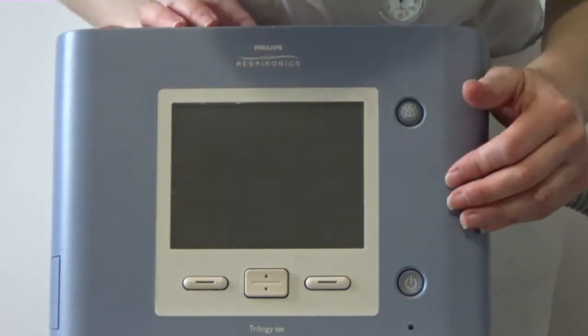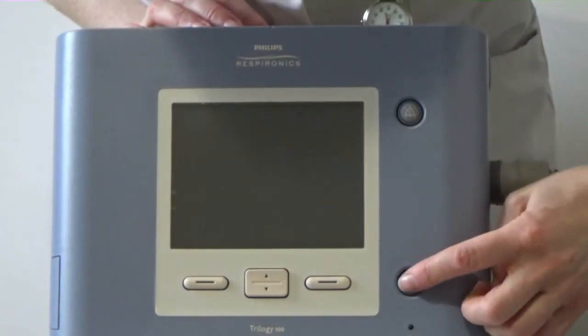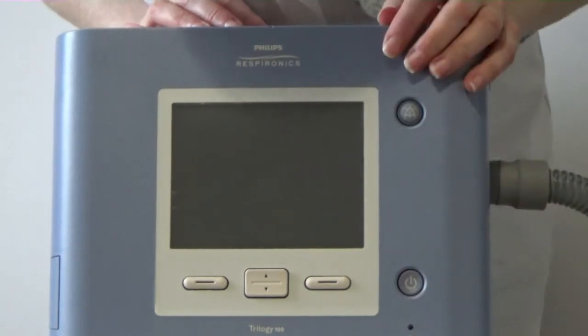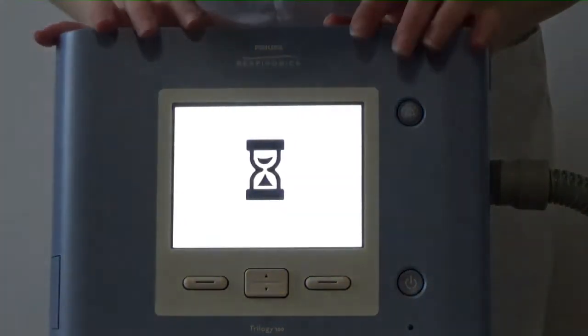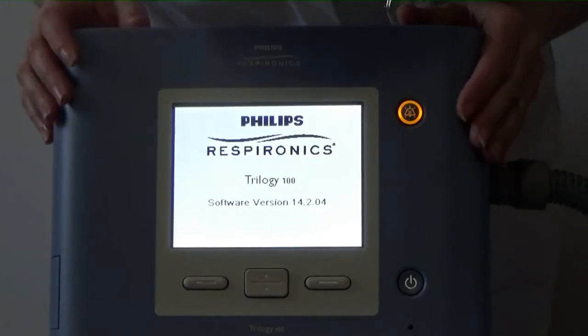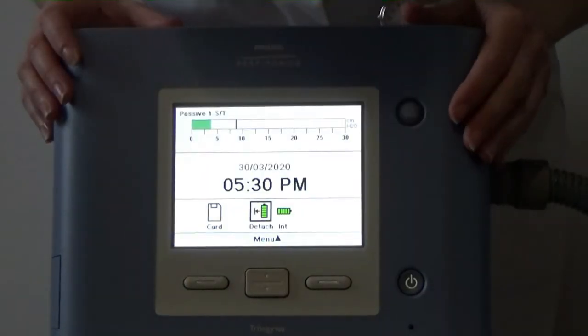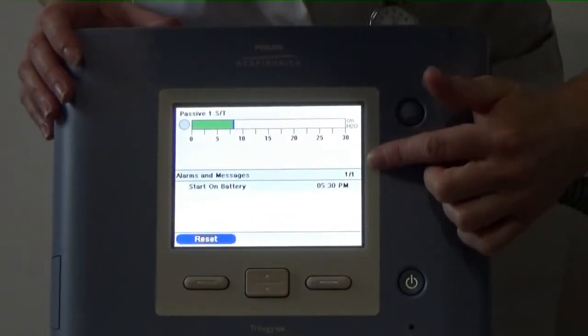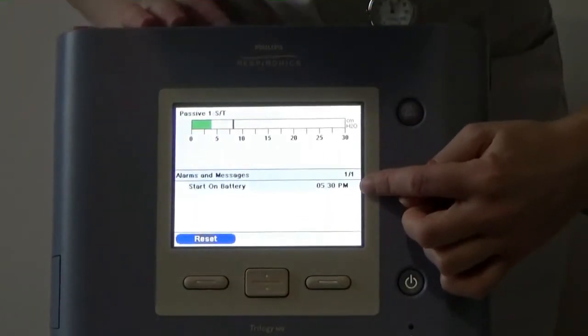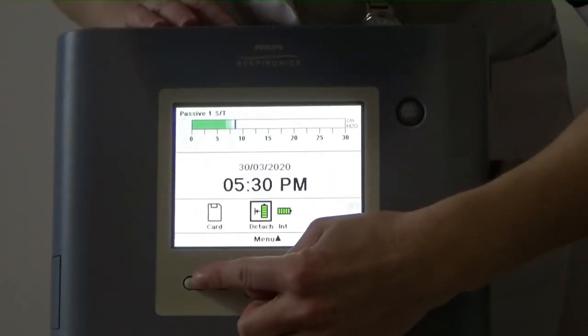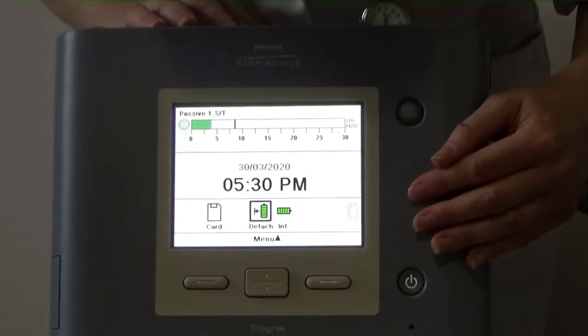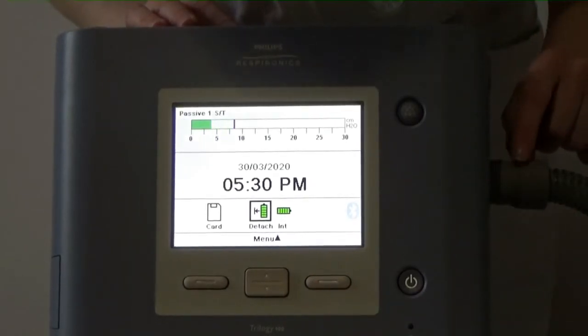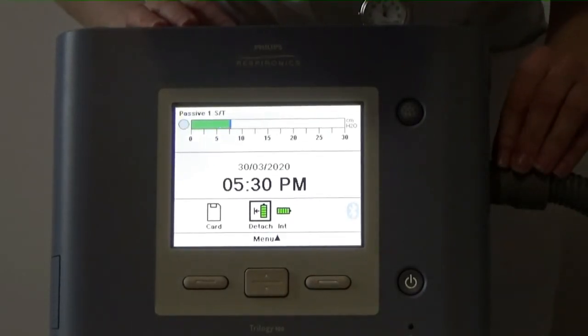We're now going to look at operating the device. To switch the power on, press this button. Now at the minute this ventilator is working on its battery. So you see, as soon as we switch it on, it comes up with an alarm that says start on battery, and we need to press reset to select that.